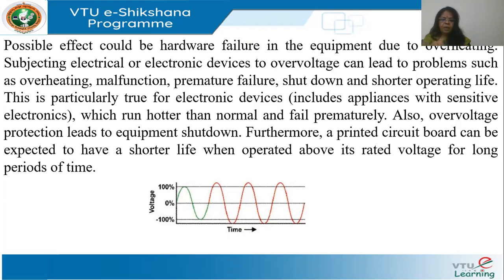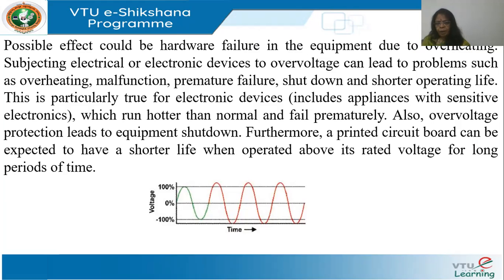Whenever an electronic component burns, first look for an over voltage — that is one of the main reasons. Over voltage protection relays have a set threshold and will operate to shut down equipment. A PCB will also have a shorter life if operated at a greater voltage than its rating.